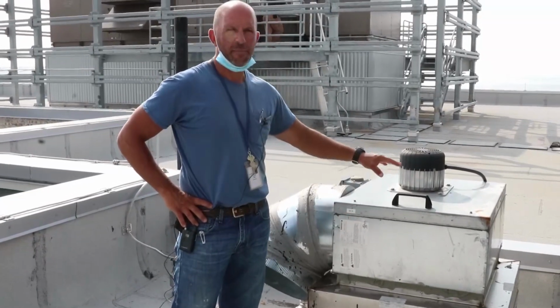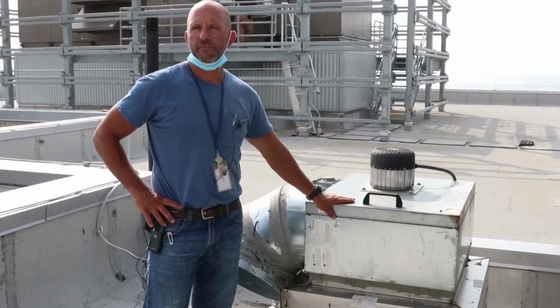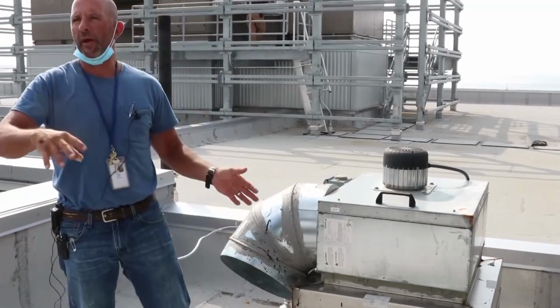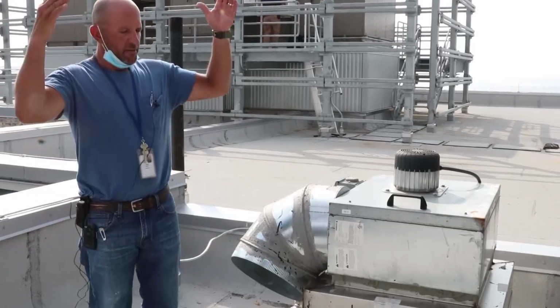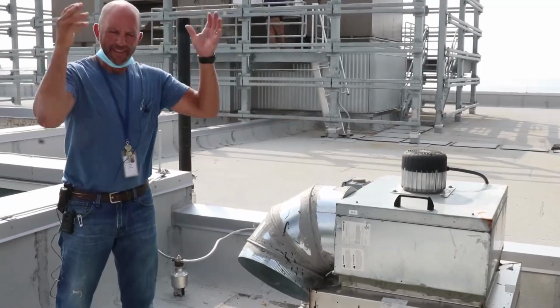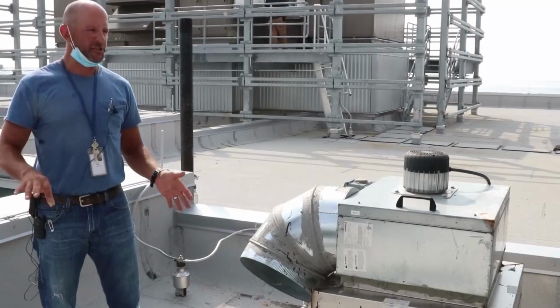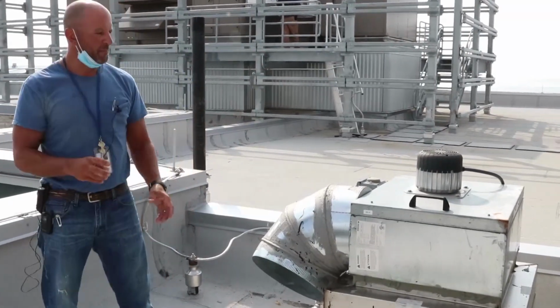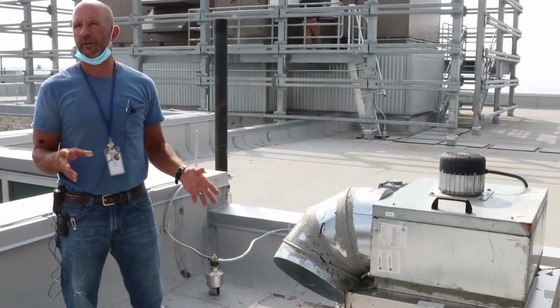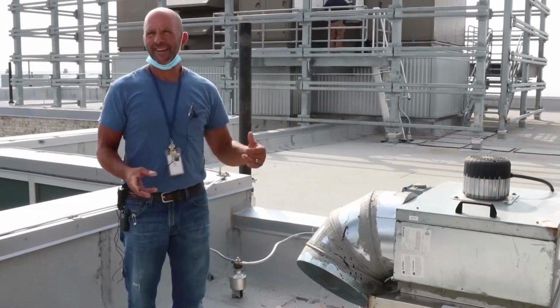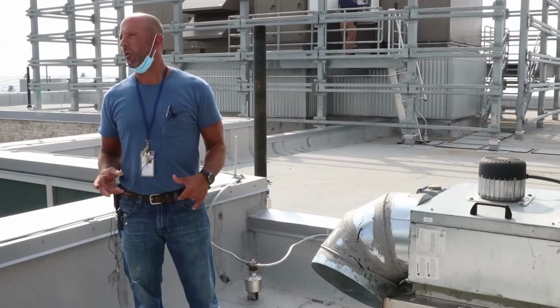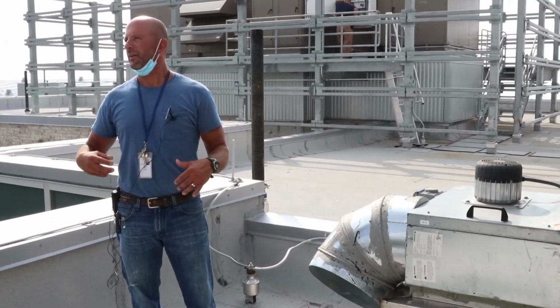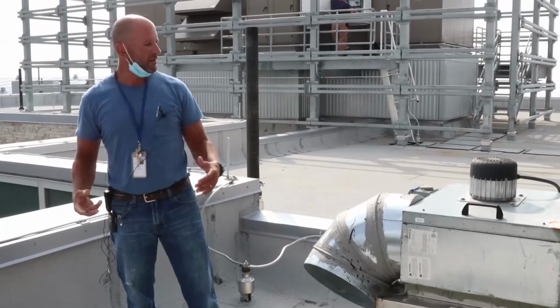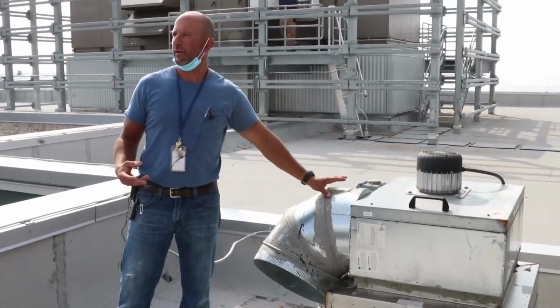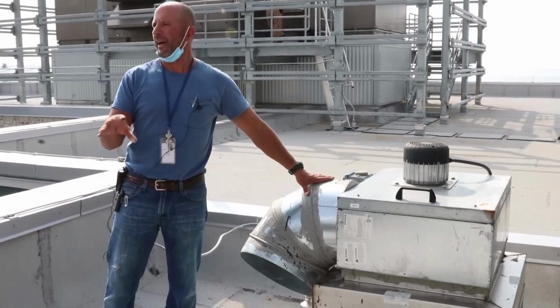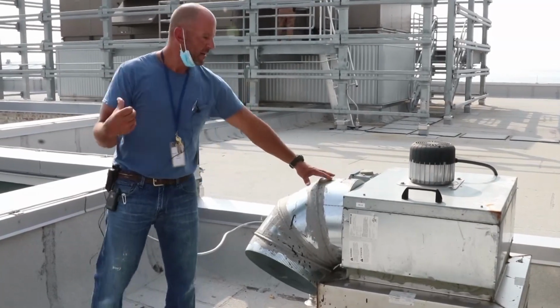These fans are basically tied into every dryer that you have in this bank, in this wing. As you go down the riser, there's a piece of round pipe that comes over and down, and breaks out of the shaft. It's like the ductwork, and it picks up each one of these dryers individually. There is a pressure transmitter at the base of the run, so as more dryers come online, it knows it needs more airflow, and it'll speed this fan up based on the pressure transmitter reading, which goes back to a head-end controller, which I'll show you in the closet.